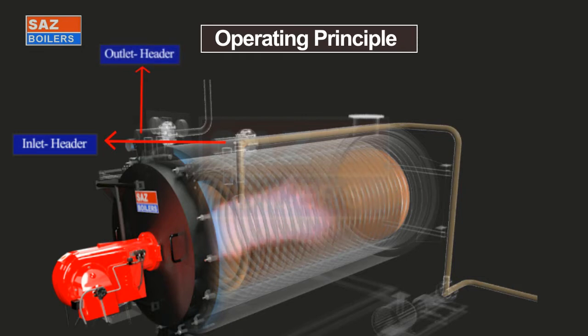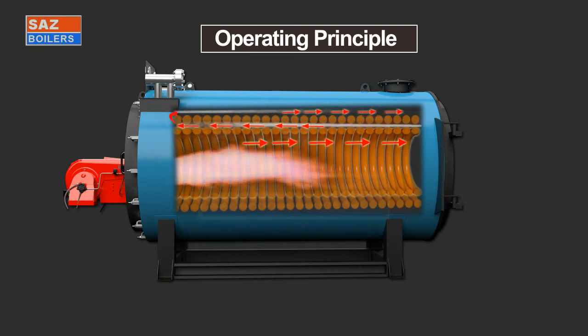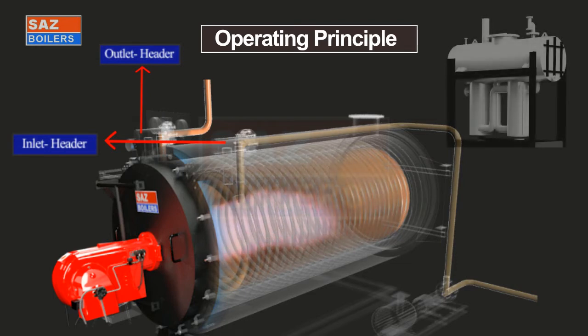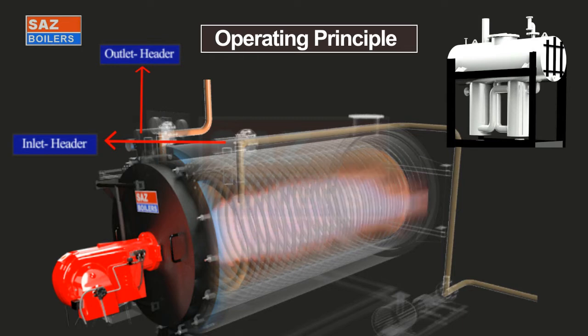Heat is transferred by radiation and convection from flame and flue gas in three passes to the thermal fluid. After the first pass, second pass, and third pass, flue gases exit to the chimney. Hot thermal fluid is circulated through the process equipment. Return thermal fluid is passed through the deaerator tank to remove any vapors. The expanded thermal fluid goes into the expansion tank, which is fitted at the topmost height of the system.